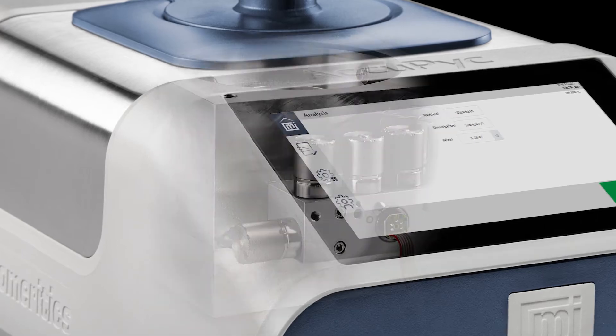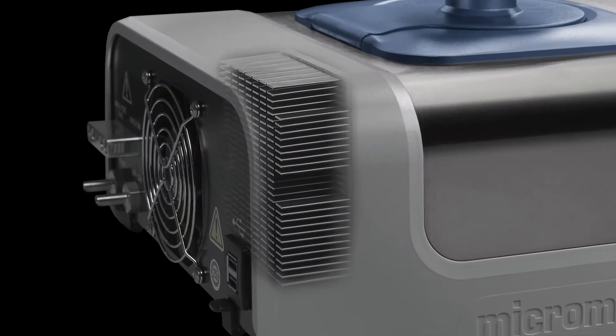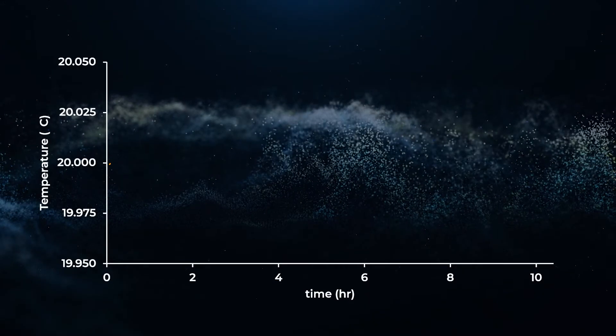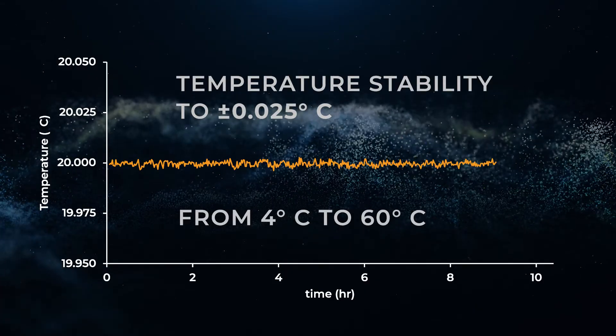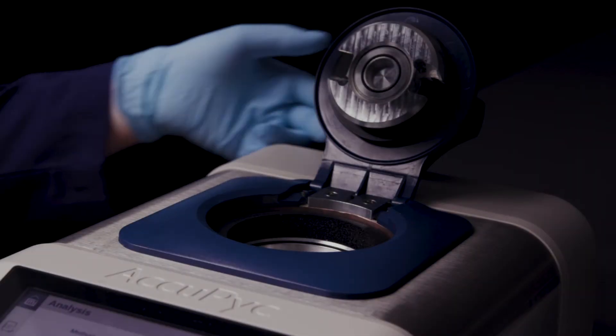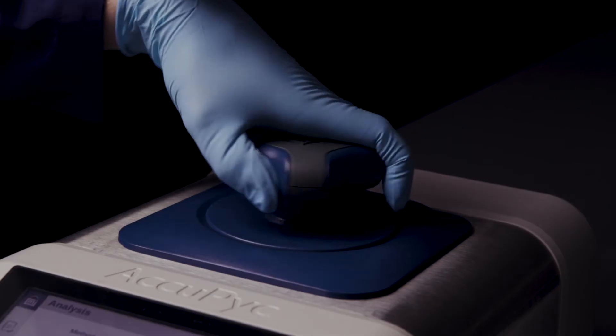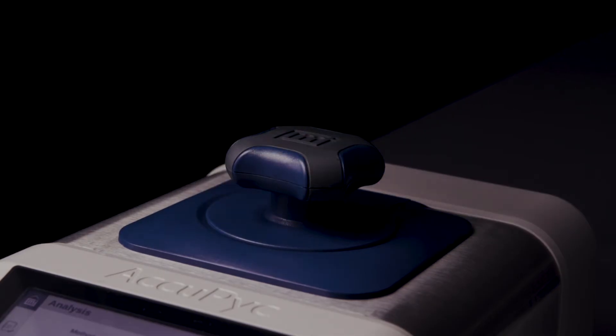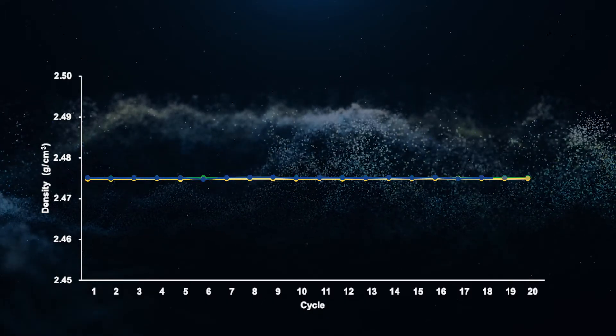Accurate density measurements require temperature stability. That is why every AccuPyc features a high mass single block design plus ACUTEMP, which guarantees temperature stability to plus or minus 0.025 degrees Celsius over the widest range of available temperatures. Combined with advanced gas modeling and repeatable cell closure, the AccuPyc produces the most precise and reproducible measurements for every user, every time.